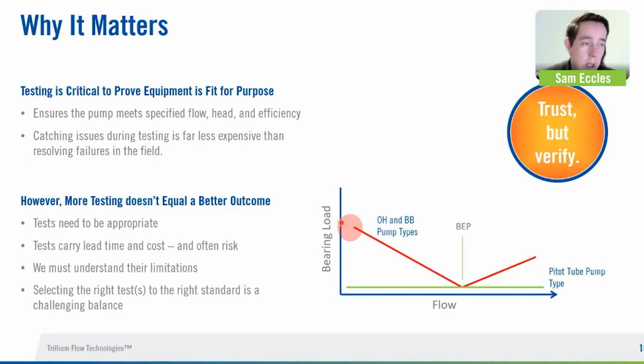I won't go into too much detail on this, but essentially, if you have designed a unit to operate on a light hydrocarbon, that bearing load will be much, much lower than it will ever see operating on water. So you can introduce risk by going back here. And even on high energy pumps that are designed for water, running there at any length of time increases risk, increases the probability of failure. And just generally, the more stop-starts you have on the pump, the more opportunity there is for something to go wrong. And we need to be aware of that when we're specifying tests.